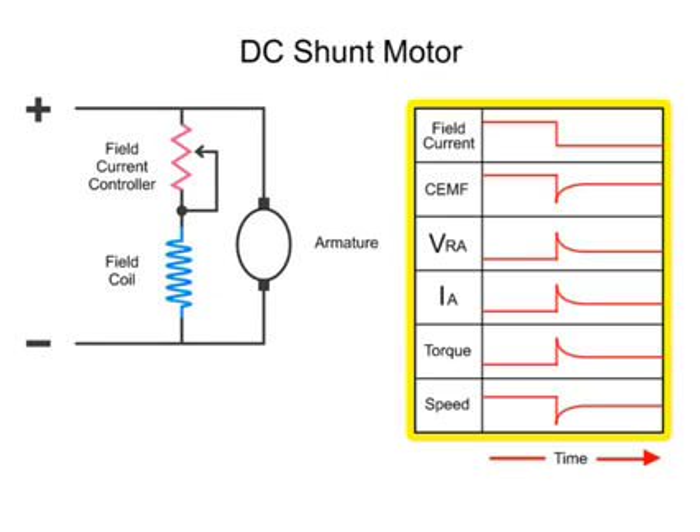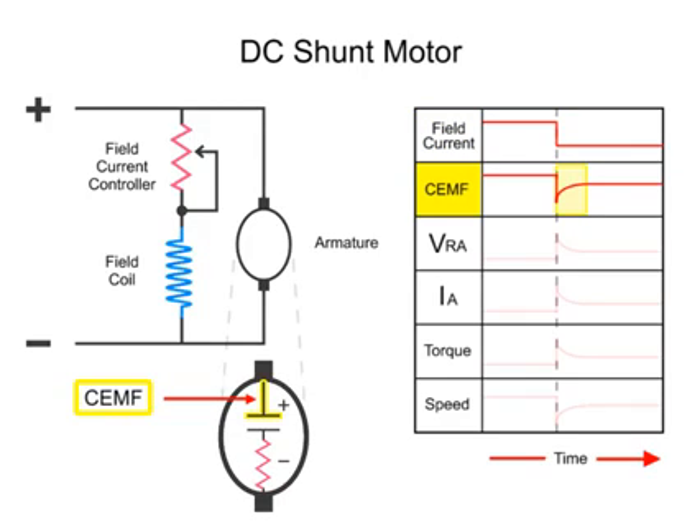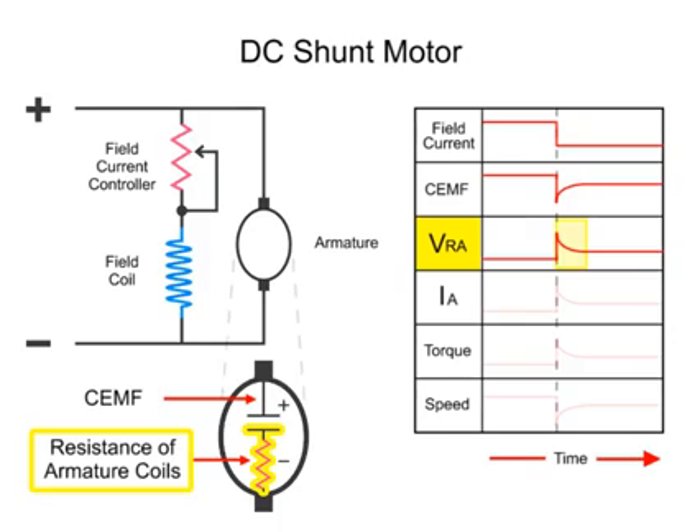Here we have a series of line diagrams to illustrate the relationships of the motor properties as a result of reducing the field current. When the field current is decreased, the counter-electromotive force or CEMF drops off dramatically. This sudden change results from a reduction in the EMF generated in the armature coils which are turning within a less dense magnetic field. The less dense magnetic field is a result of the lowered field current flow. This also causes a spike in the voltage drop across the resistance of the armature.